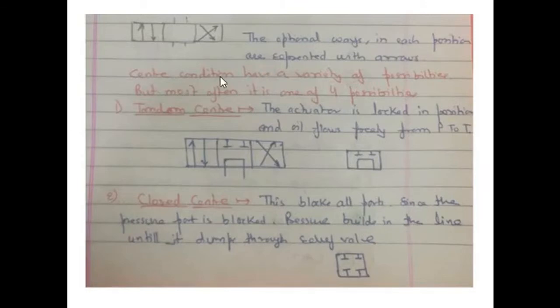Center condition has a variety of possibilities, but most often it is one of four possibilities. Number one is tandem center. The actuator is locked in a position and oil flows freely from port P to T. Here you can see the oil from port P, pressure port, is flowing back to tank port.